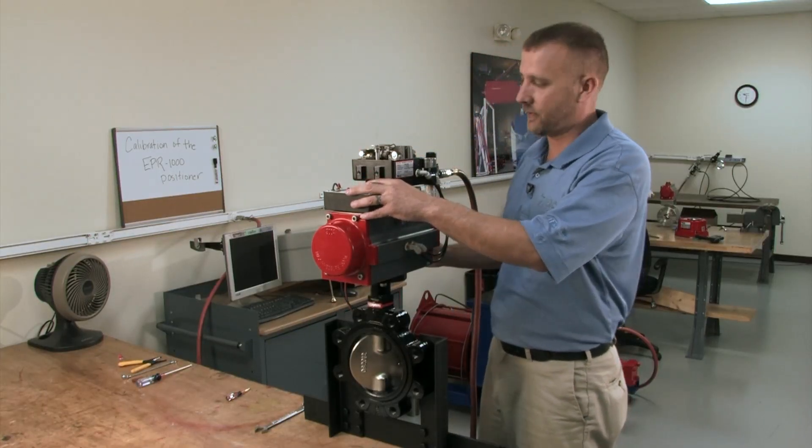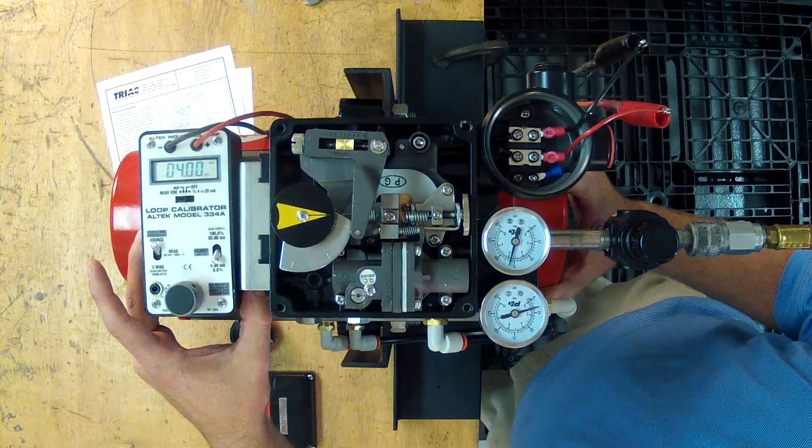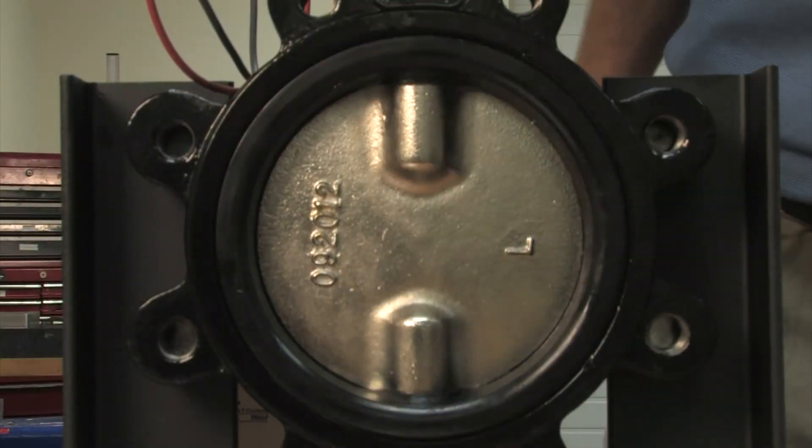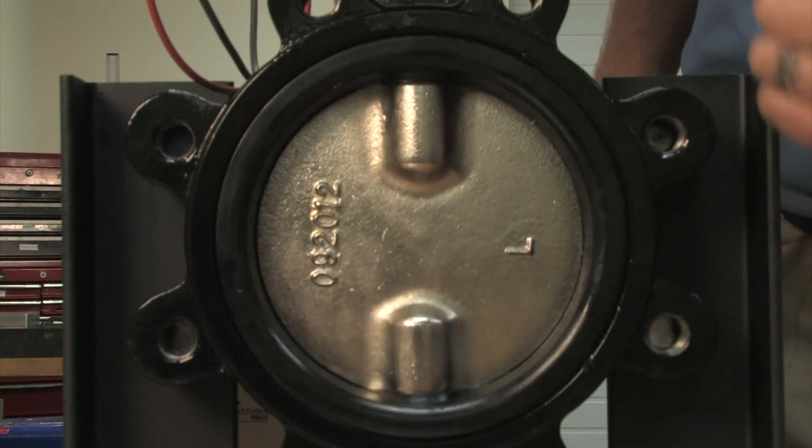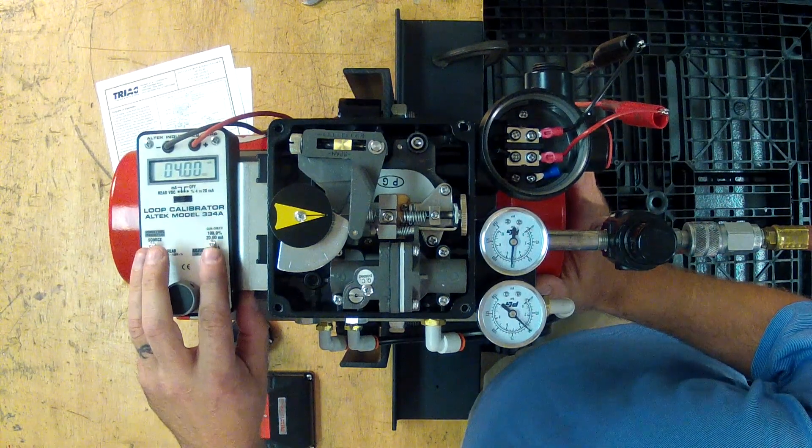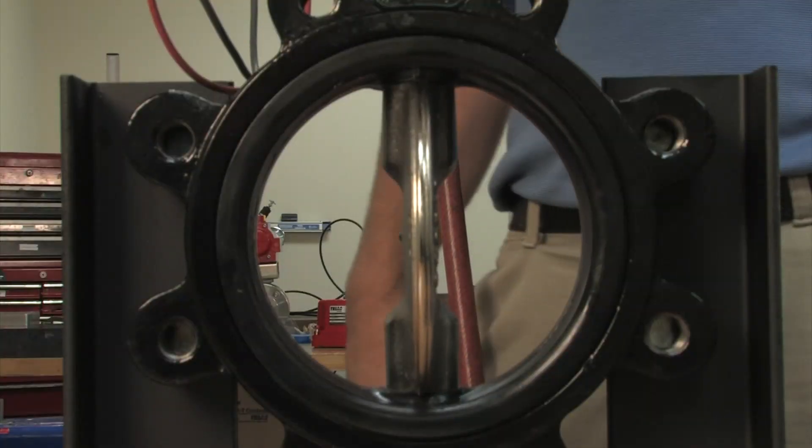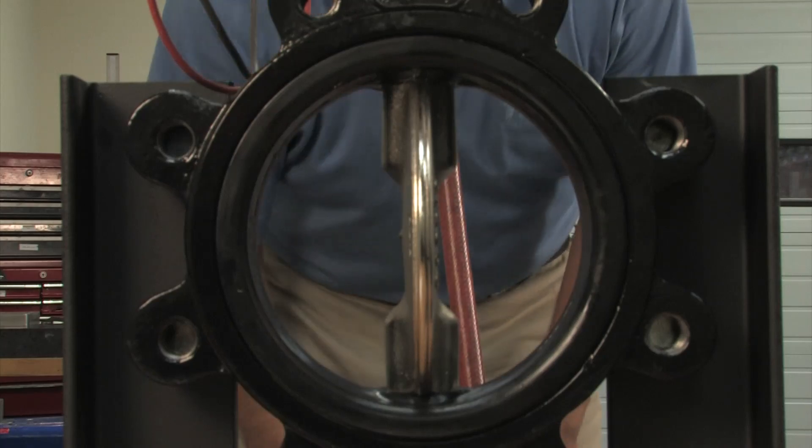So now we're going back down to 4 milliamps. And you're looking for a nice even seat in your valve, which we have here. A nice even distance on this side to this side. Back to 20 milliamps and you want a nice straight through parallel to the actuator flow pattern.